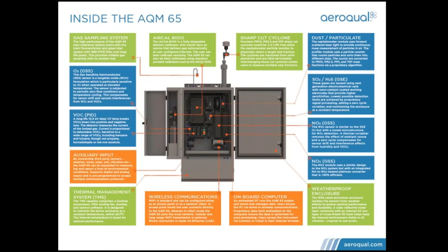This slide, which again I won't go into in high detail as it would take some time to work through, shows an inside view of a typical AQM65 station. We've tried with this infographic to reveal what's inside the box, so to speak. On the side you can see we have a calibration chamber - an option that allows remote calibration of the instrument, much in the same way a US EPA station has an automated calibration regime. This calibration system is very similar, allowing remote calibration of the zero and span for several of the gas modules.